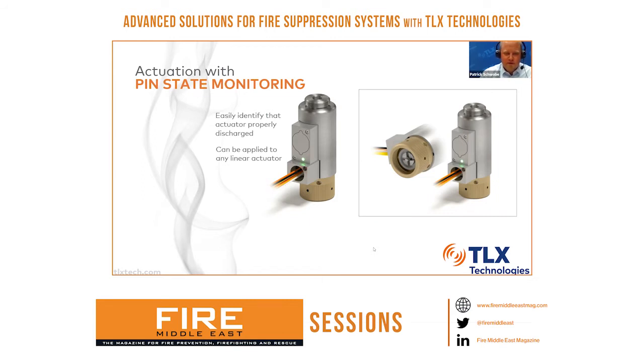What we're really trying to avoid here, and what we're trying to do, is give the installation technicians the ability to know that device is staged and prepped, ready to be installed onto the discharge valve. There have been cases where the linear actuator is removed from the discharge valve during periodic maintenance, is tested and fired, and then the technician went to put it back onto the discharge valve, which potentially causes an accidental discharge of that system based on the pin being extended and coming in contact with the Schrader valve. The unique thing is this technology can be applied to any device in that family of linear actuators.